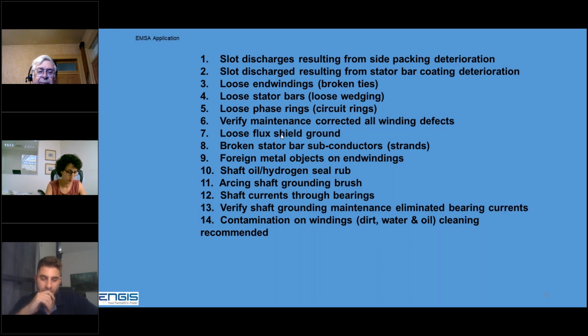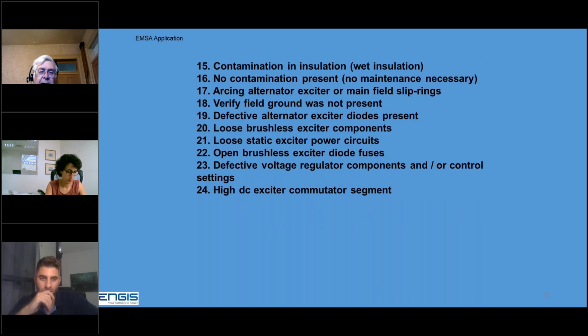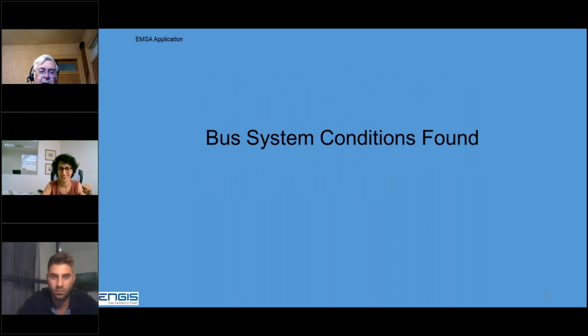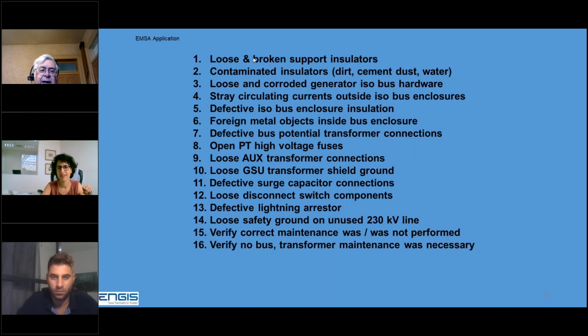Flux shields, this was on a big Brown Boveri generator. Contamination, alternator or main field slip ring sparking. Defective diodes we talked about. Brushless exciter, we found one down in the Dominican, oh no, it was in Jamaica. A brushless exciter that was ready to explode because it was so bad. Power cable problems.